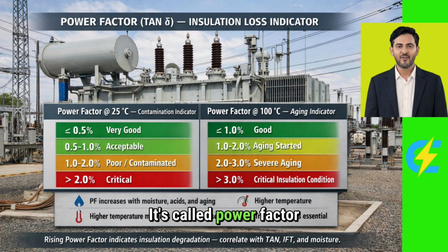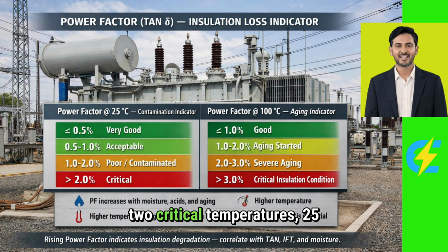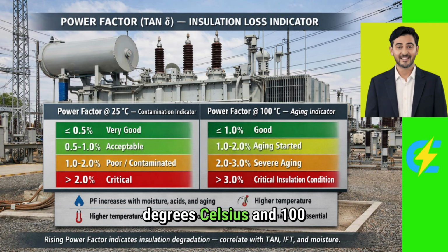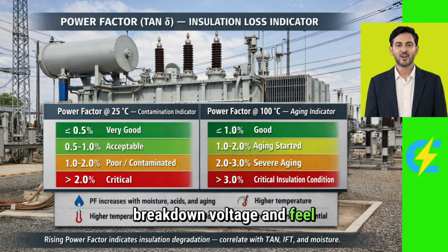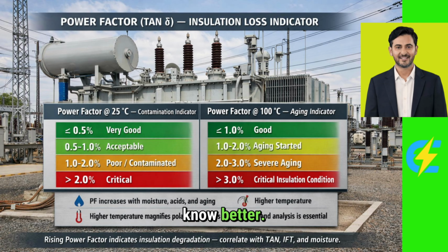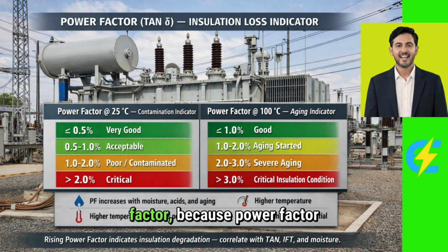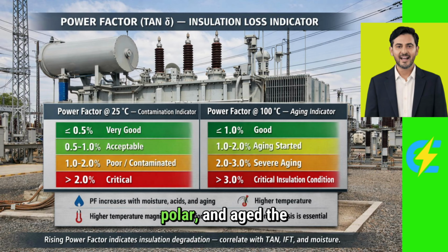It's called power factor testing, or tan delta, and it's measured at 2 critical temperatures, 25 degrees Celsius and 100 degrees Celsius. Many engineers look at breakdown voltage and feel confident about their transformer oil, but experienced engineers know better. They look at power factor, because power factor doesn't test how strong the oil is for one moment. It tests how dirty, polar, and aged the oil has become over time.